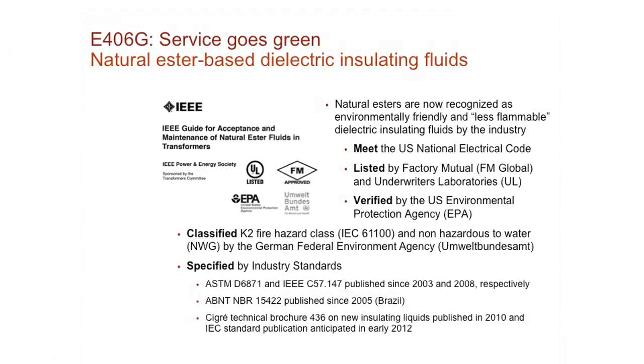The natural ester-based product here, as you see, has the FM and the UL ratings. It does meet the U.S. National Electrical Code, the FM and the UL, as I said, and it is verified by the U.S. Environmental Protection Agency. Also, back to the fire safety, it is classified as a K2 fire hazard. It does pass the K2 fire hazard class test, and it is specified by the industry standards.